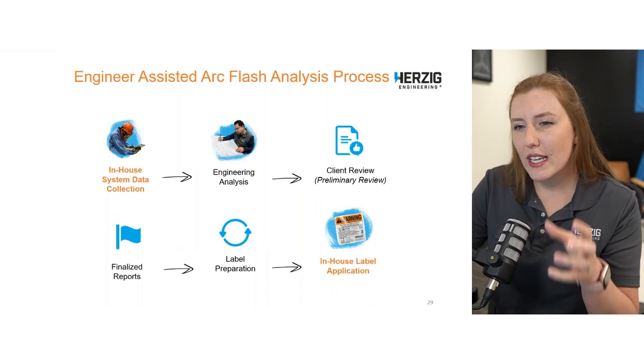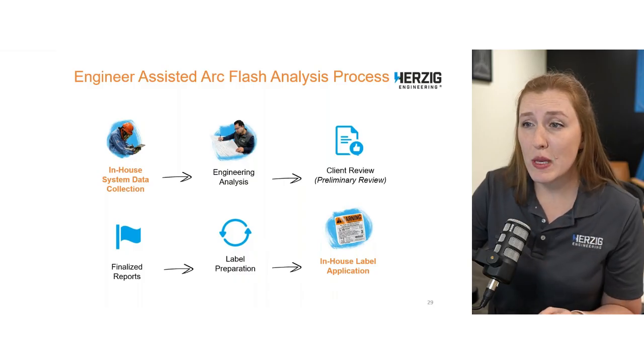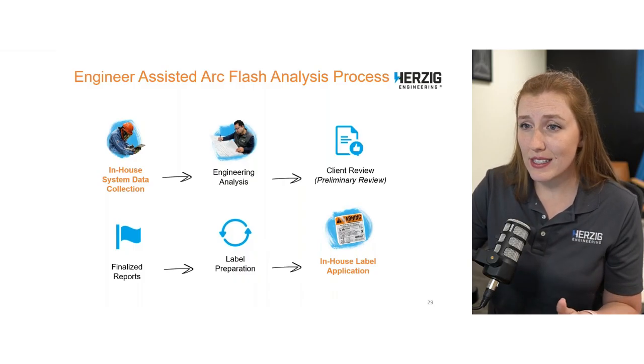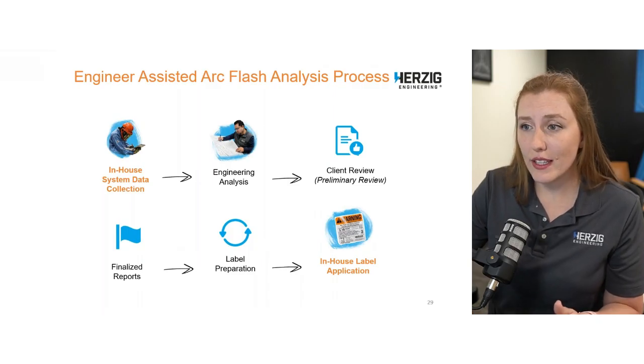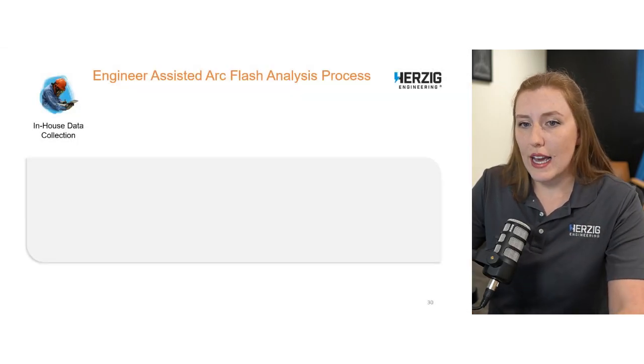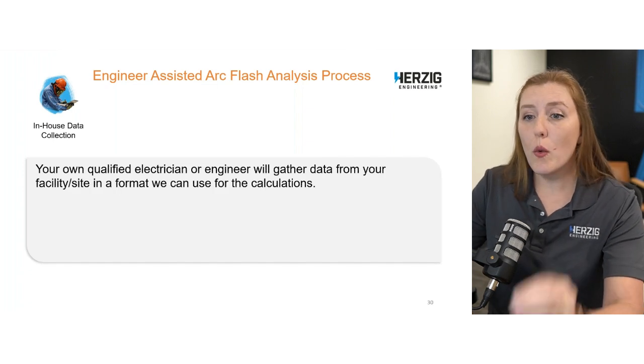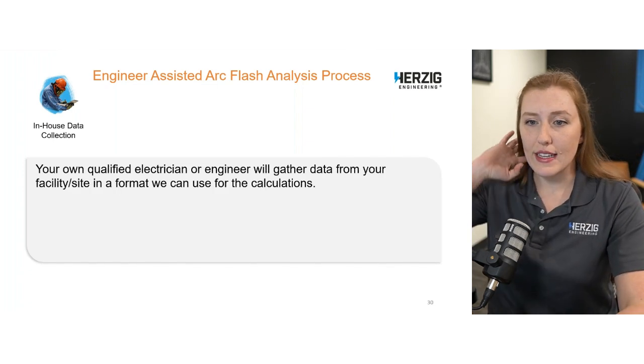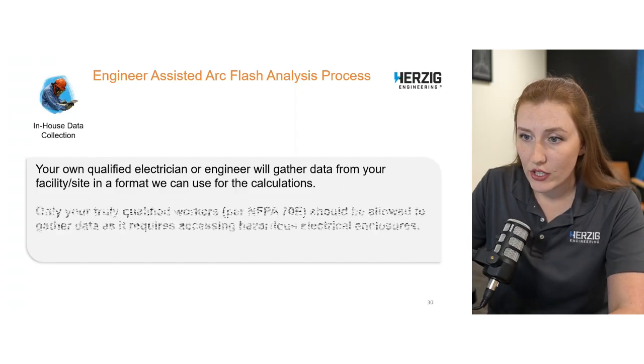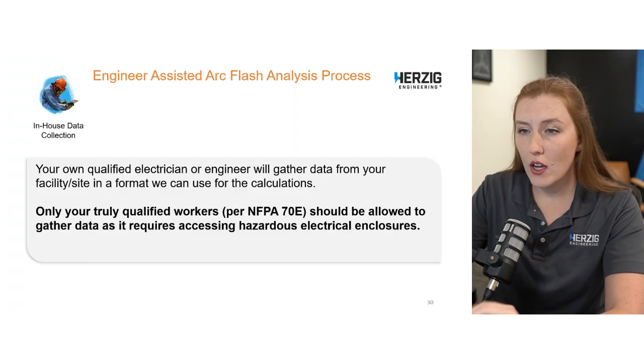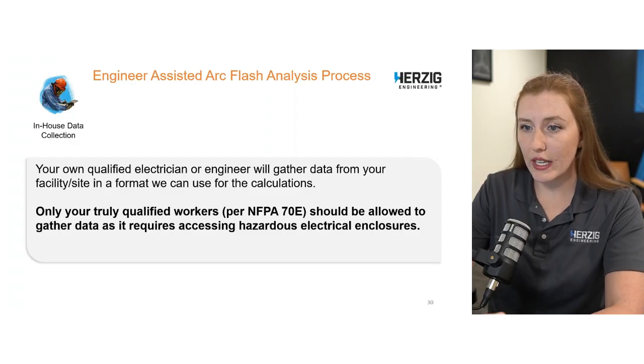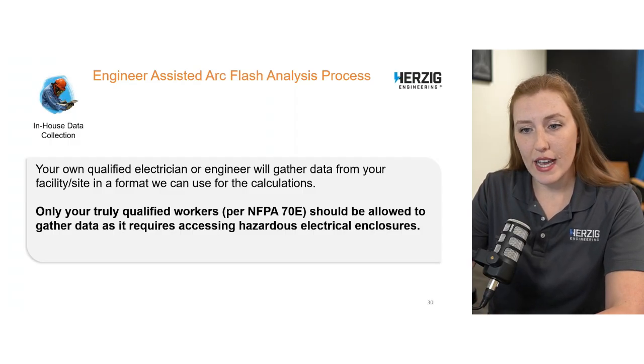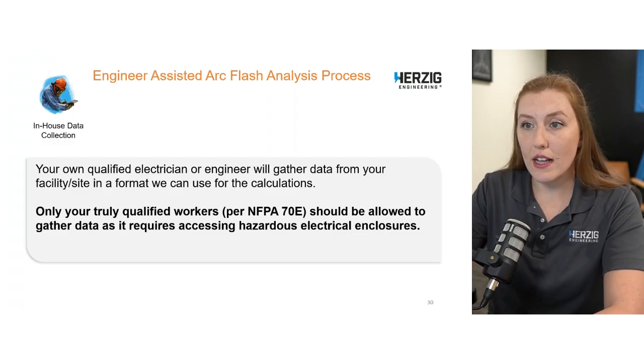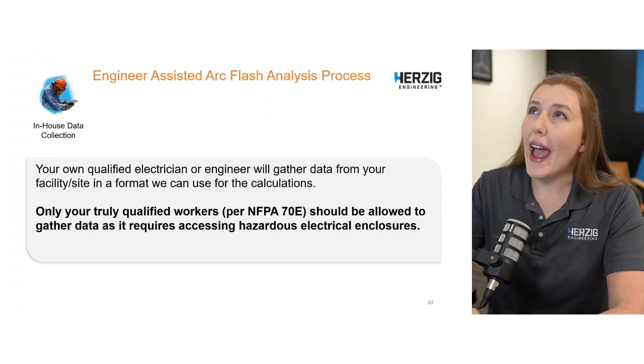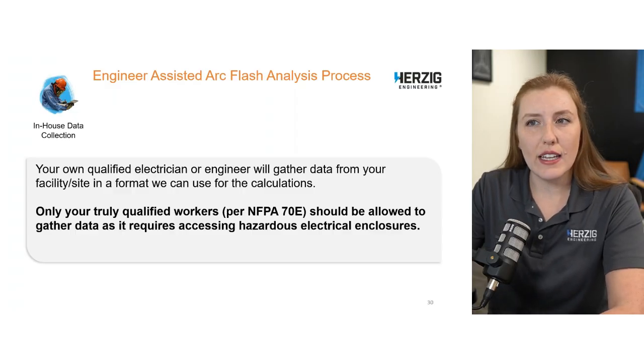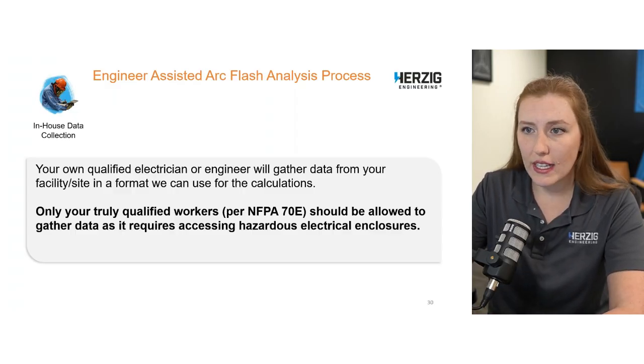Okay, so what are the key differences here? Well, you're going to have people who are qualified and able to collect this data and then go back and apply the labels. So what about this data collection thing? Well, your own qualified electrician or engineer would need to gather that data so that we can then perform the calculations. You have to be very careful here. Only truly qualified workers per the NFPA 70E should be allowed to gather this data. It does require accessing hazardous electrical enclosures. You don't have to collect this data while it's energized. It's not like an infrared scan, right?